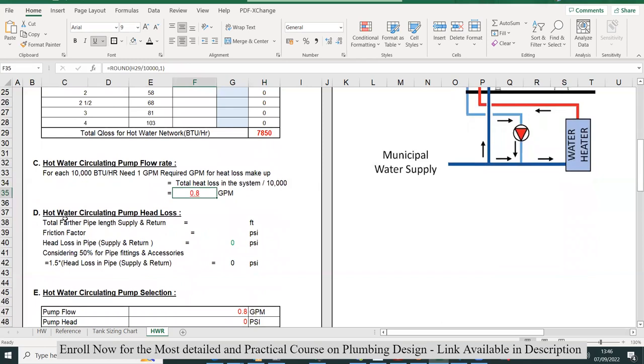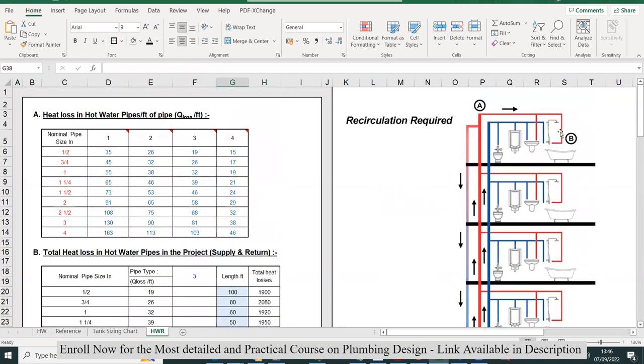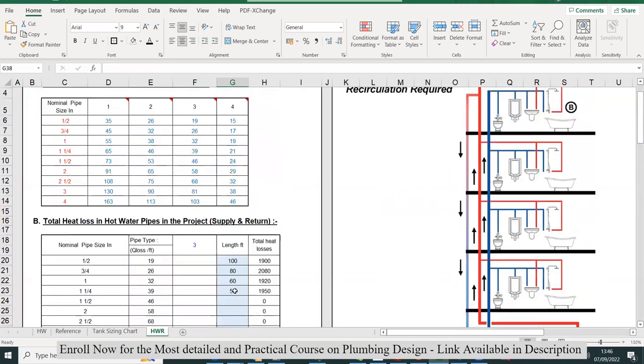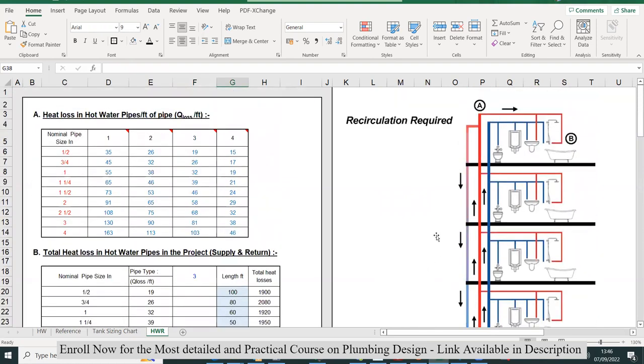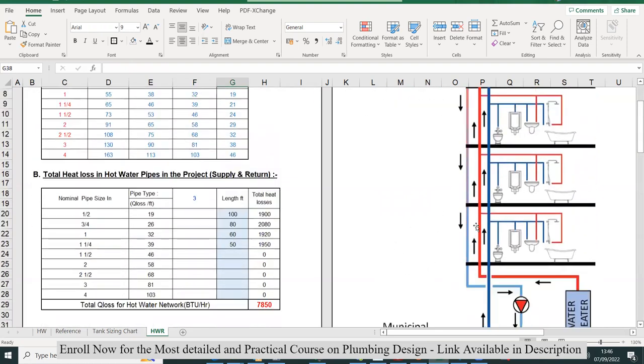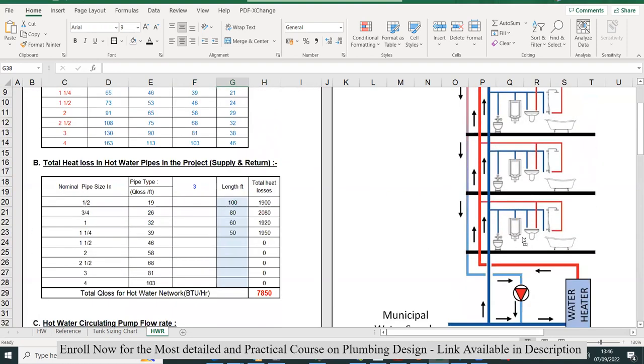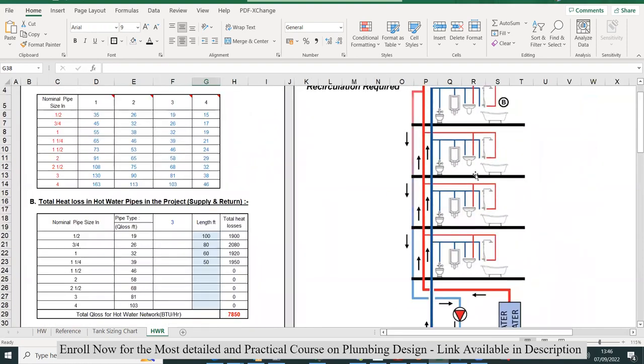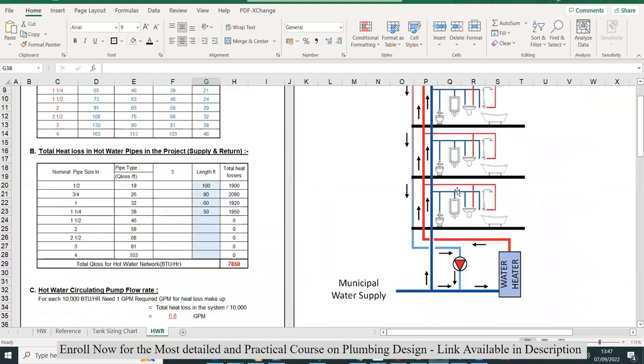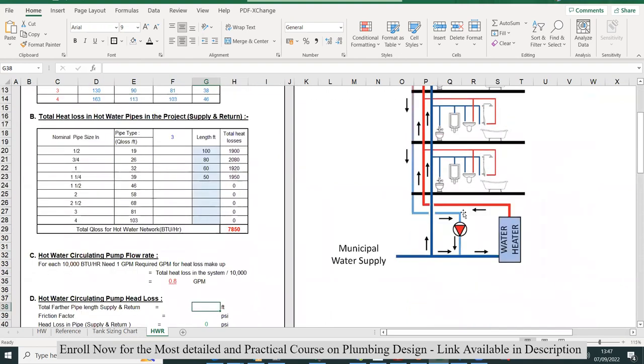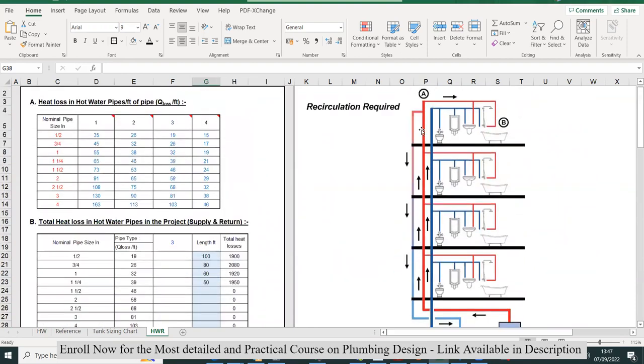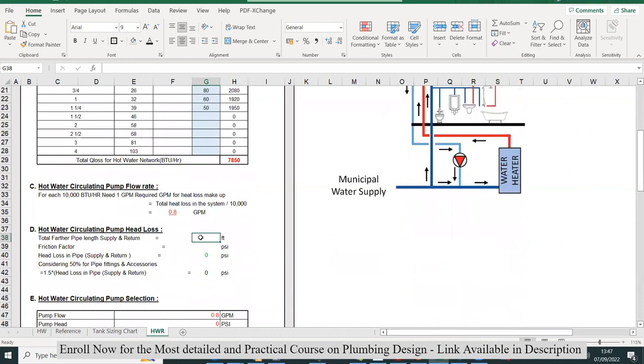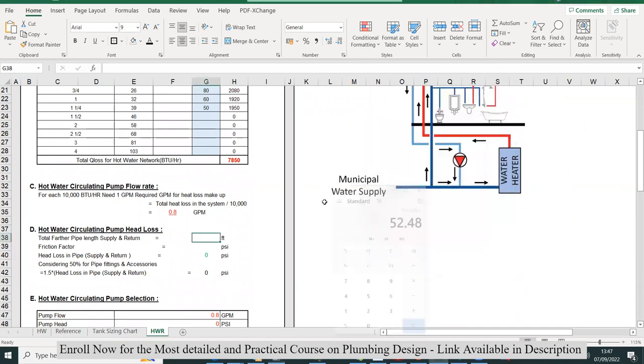Section D will calculate the pump head loss. For pump head loss, you have to write what is the total piping length up to the remote fixture. For this case, I'm assuming it's a four-story building. So four times three is 12 meters, plus I'll assume two meters above, two meters below—that's 16 meters. I'm assuming 16 meters as the critical pipe length. I'll multiply this value because 16 meters is the supply. 16 times 3.28 gives you 52 feet as the pipe length.